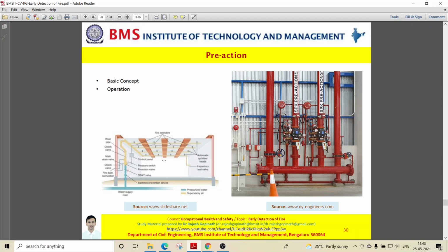Now, the operation of this valve is controlled by an independent flame, heat or smoke detection system. Please understand, if the sprinkler has to activate, then two separate events must happen. First, the detection system must identify a developing fire. When it does, it should open the pre-action valve. When it does that, it allows water to flow into the system piping, which effectively creates a wet pipe sprinkler system.